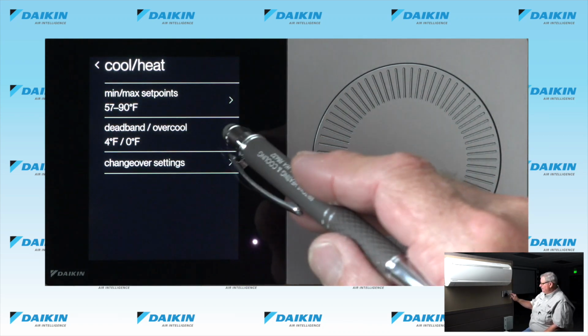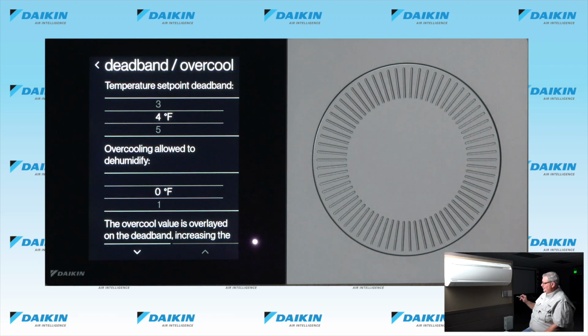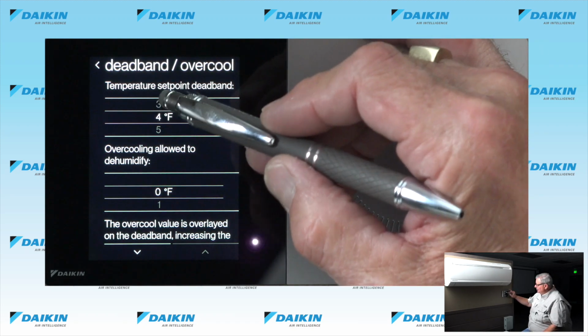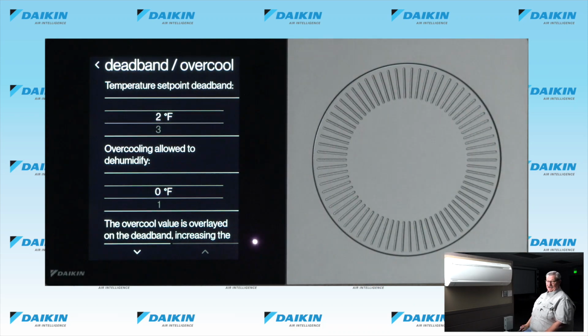Dead band. We are going to change our dead band to 2 degrees. It's a real nice feature, being able to get that down as close as possible. It is adjustable from 2 to 10 degrees. This is the dead band for the reversing valve changeover from heating to cooling.